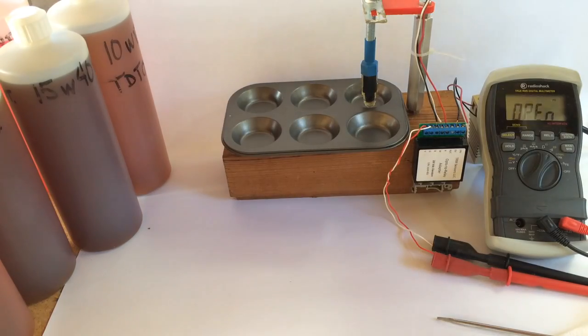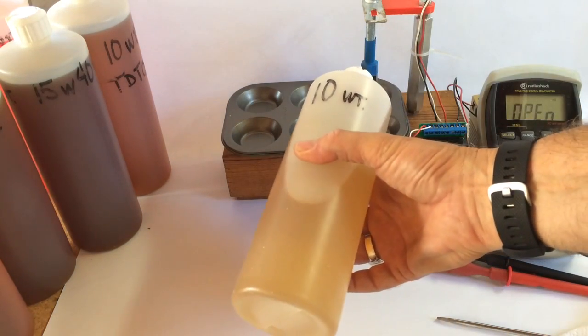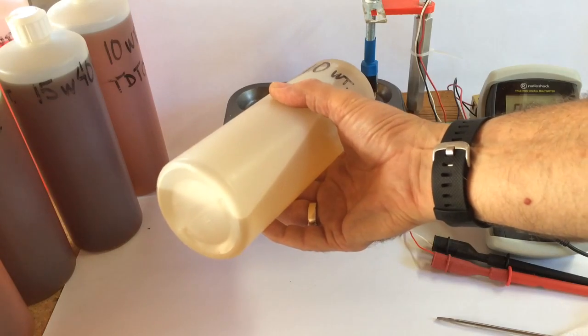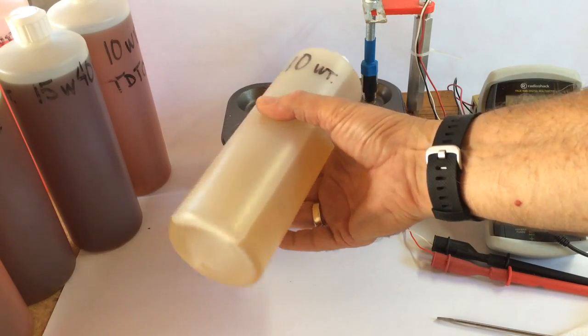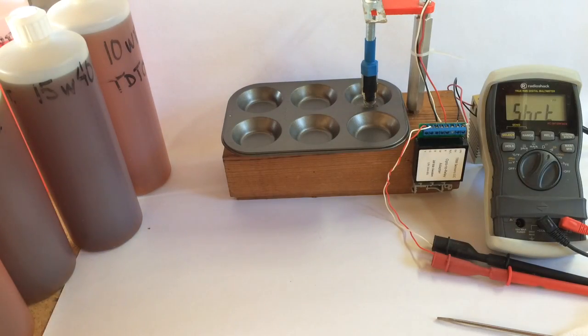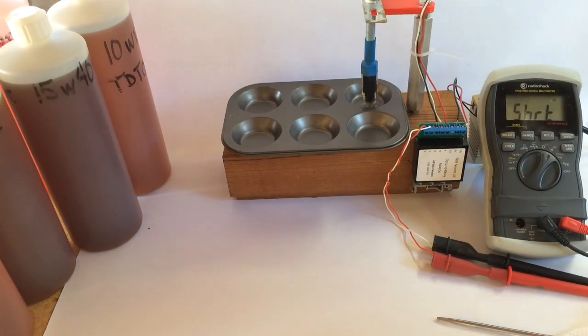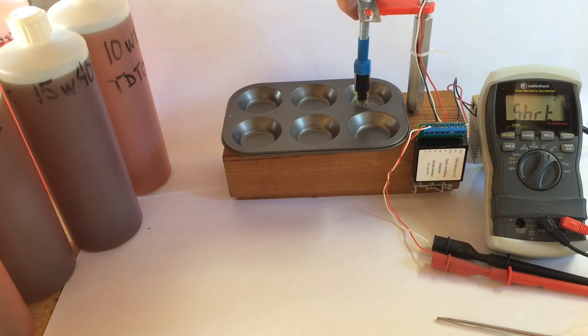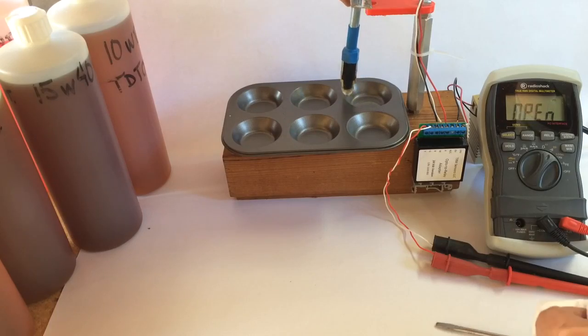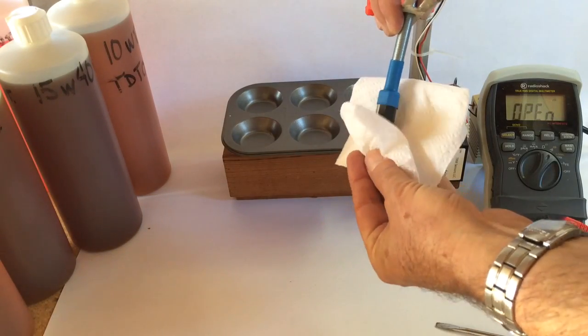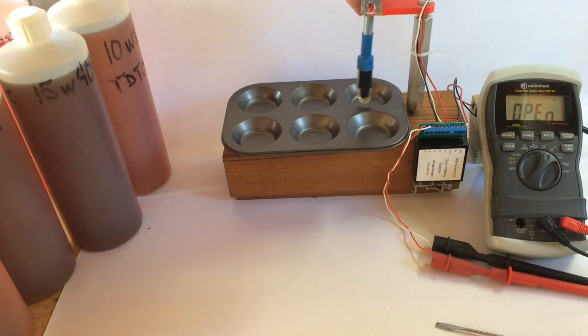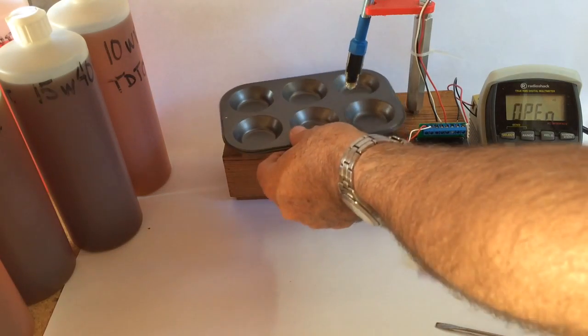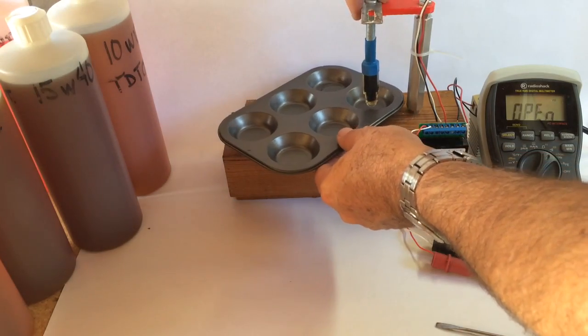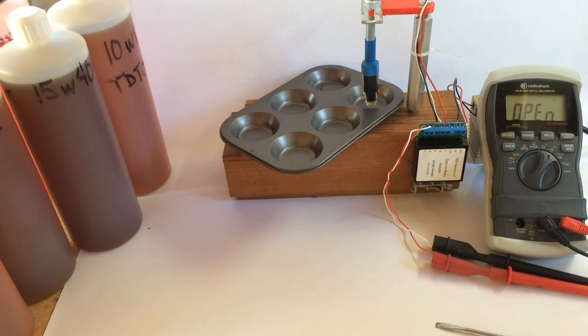So what we're going to do is just add a little bit of fluid to the muffin tins, and in that case we got a response very quickly. This was 10 weight motor oil, and probably no more than about a 1/16 of an inch deep. We'll actually measure that at the end of the test. So it resets when it comes out of the fluid. I'll wipe it off, put it back into the next little test chamber, and now we're going to test 30 weight oil.